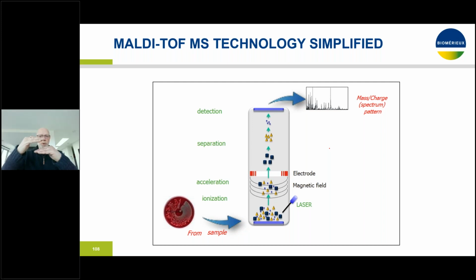And that is problem number one, because that takes a relatively long tube, a meter minimum, more or less, which means that the equipment is going to be bigger and it's going to stay bigger than the average PCR machine. And in clinical microbiology, laboratory space is expensive, so the smaller the equipment, the more appreciated that is. But this is mass spec, and there's things that you can do with this acceleration tube.